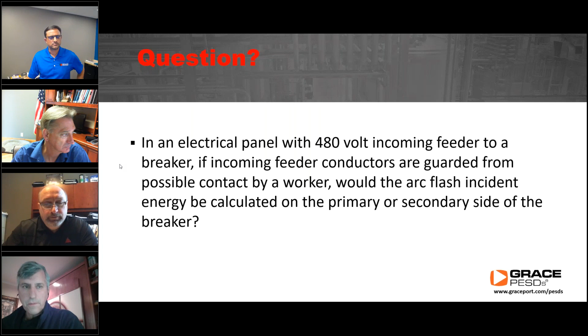So when you talk about guarding, especially Lexan shields and things like that, be very thoughtful about trusting it to absorb an arc flash event. If the event lasts longer than expected, it could easily breach the enclosure and still hurt somebody on the other side. There's quite a bit going on here, both from the engineering side and the practical safety side.